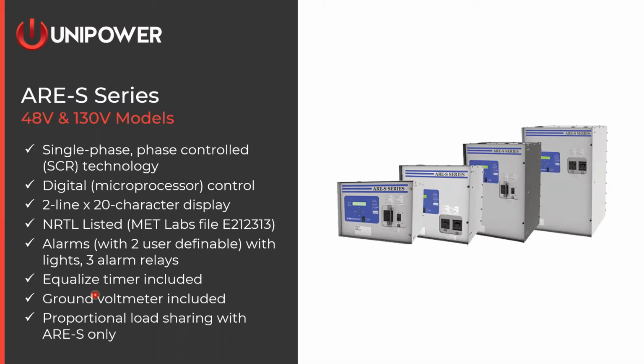They're all single-phase chargers, SCR controlled, controlled through a microprocessor, and the information is displayed on the 2x20 character display on the front panel. They are nationally recognized, listed on MET Labs file E212313, similar to the Ferro Resonant charger. And again, alarm standard with 3 alarm relays. We have 2 of those user definable. Equalizer timer is always included, as well as the ground voltmeter. And again, proportional load sharing is available, 2 or more units. You can stack up 2 or more units.